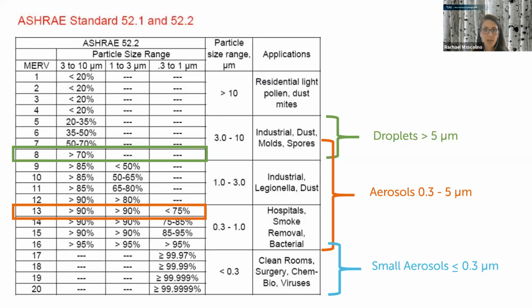MERV stands for the minimum efficiency reporting value. And a lot of people say, why MERV 13? We have MERV 1 all the way up to HEPA filtration, but you can see on this chart that MERV 13 is where we're going to start effectively capturing those small aerosol particles. And these are the respiratory particles in the air that can carry the COVID virus and other viruses in that family. The CDC and Harvard break transmission into 2 particle sizes, droplets and aerosols.